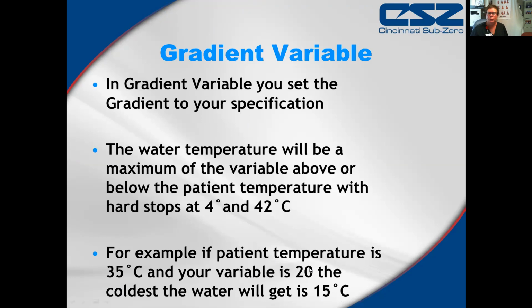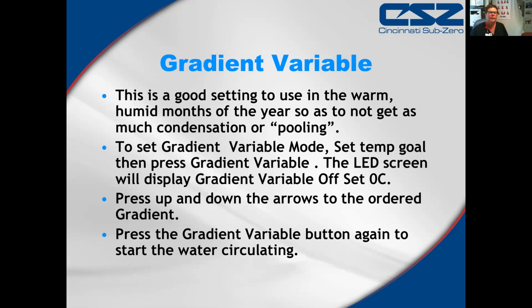So this just allows you a little bit more autonomy with the machine to allow you to reach target temperature or maintain target temperature. So a lot of my colleagues in the southern US will use gradient variable in the really humid summer months, because you may notice some condensation or pooling on the blanket itself. I've never actually encountered that, maybe because I live in the Maritimes and warm temperatures are usually not an issue. But setting the gradient variable to a little bit higher than 10 degrees will allow that less condensation to happen.